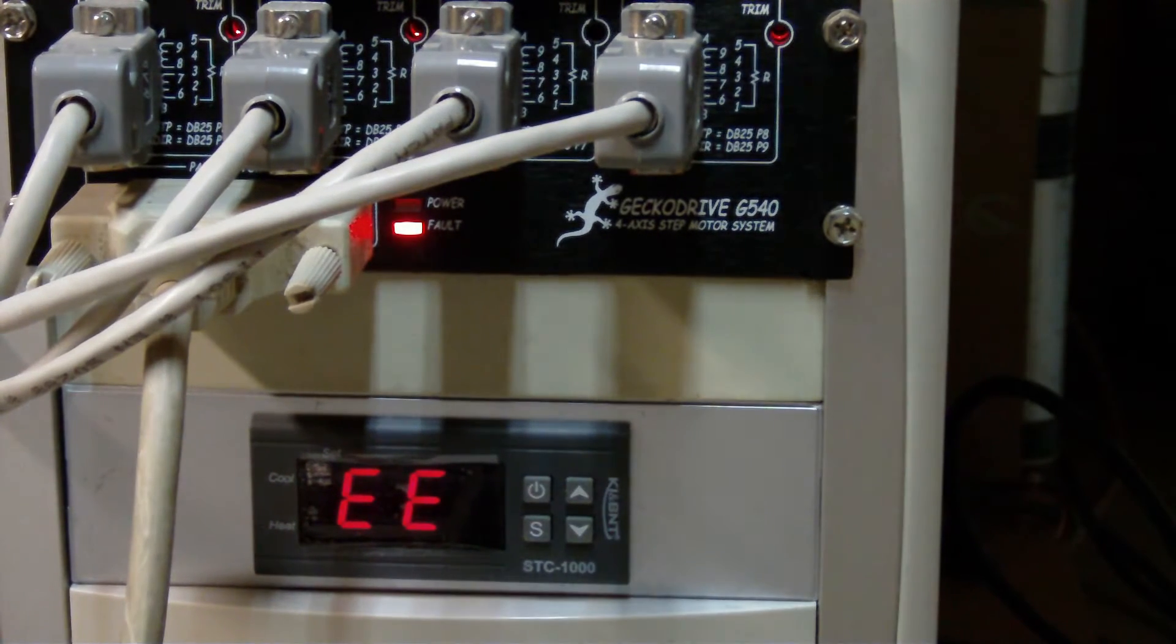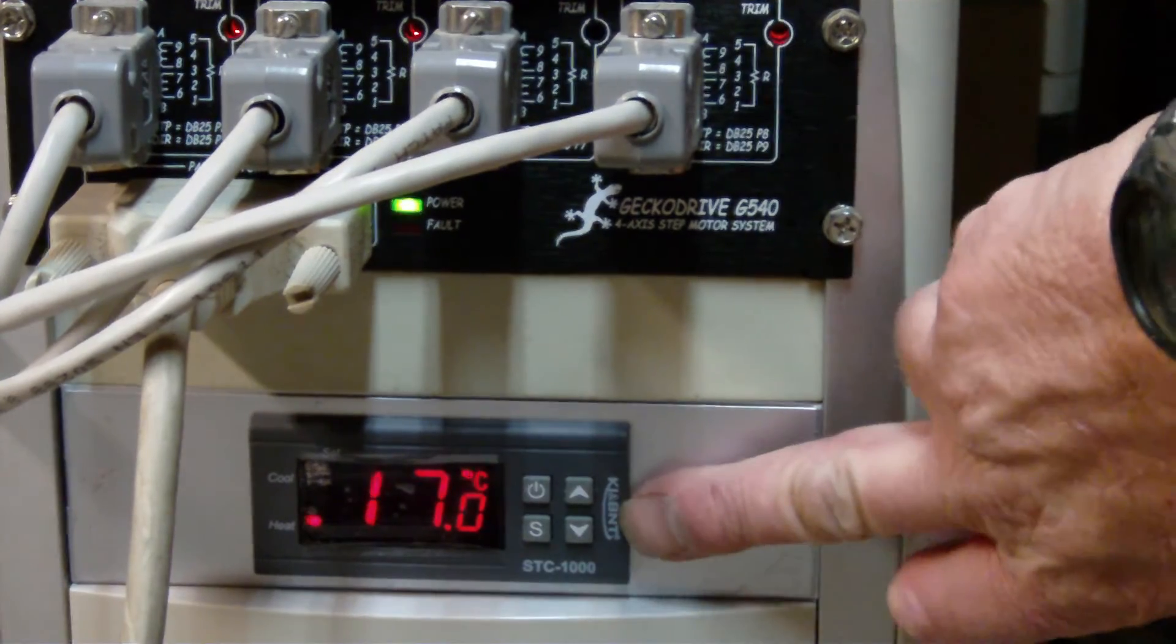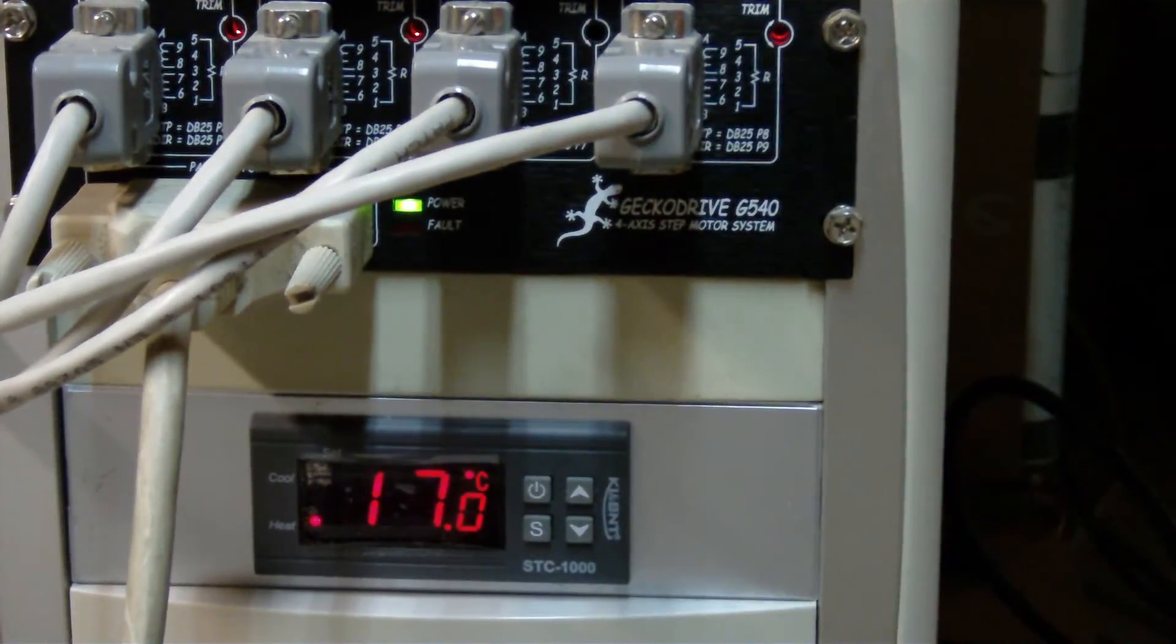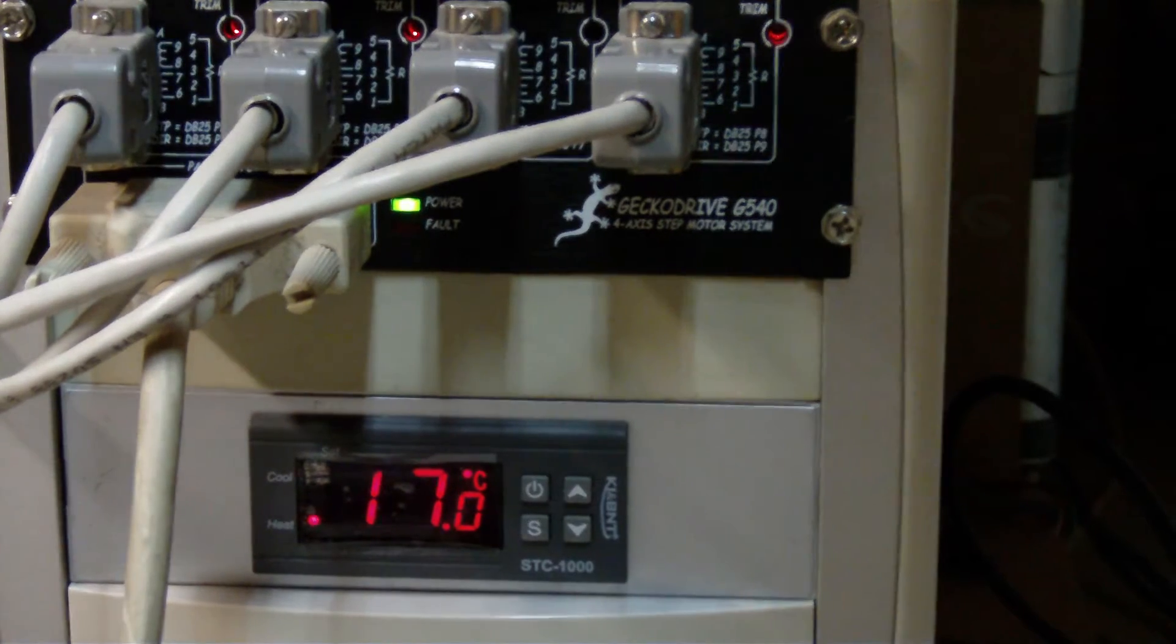If I plug the sensor back in within about 60 seconds it will have gone back and start running correctly again. There we go. We're now getting a temperature sensor reading and the Gecko has come out of fault condition.